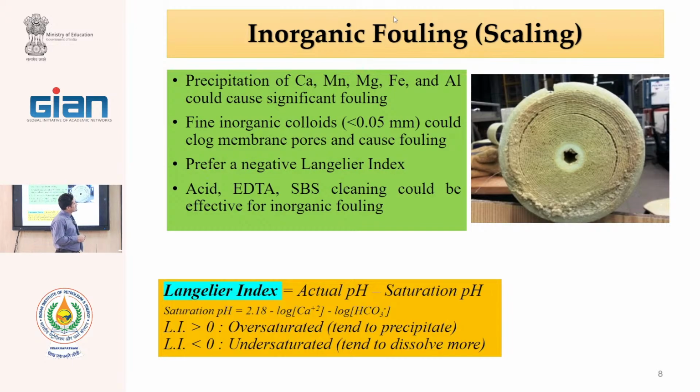In some cases, the possibility of iron and alumina in the feed is high. This can cause rapid sedimentation of the inorganic layer because the solubility of these salts is lower. The complexes of calcium and magnesium, for example with hydroxyl or sulfate, have low tendency, but the tendency of heavy metals for precipitation is high.